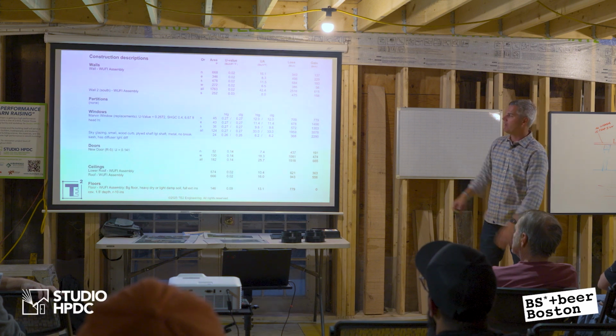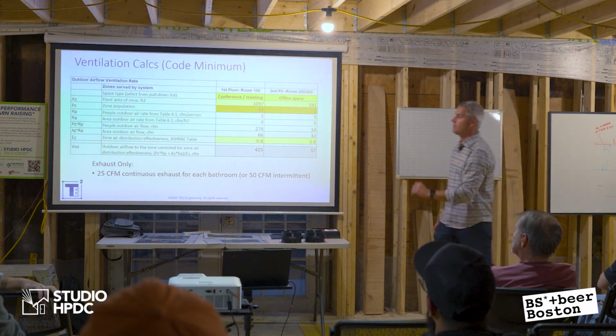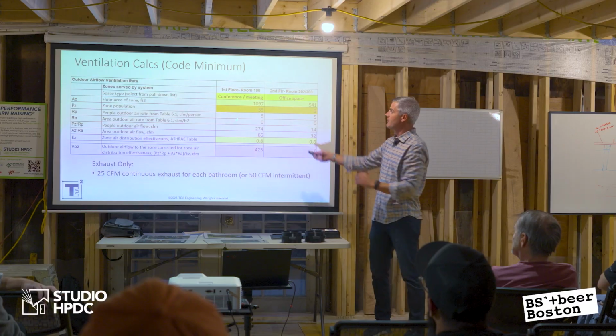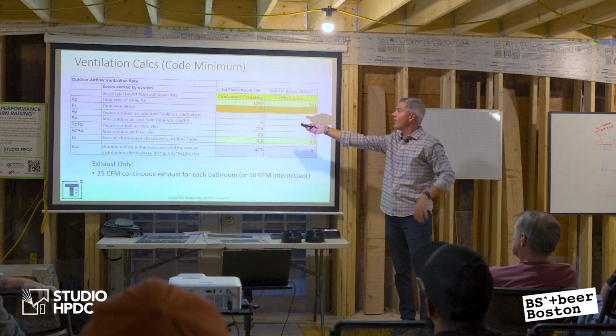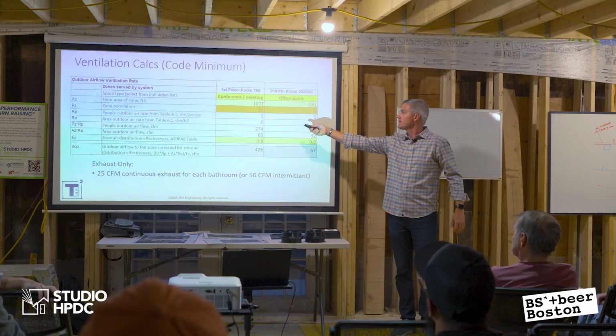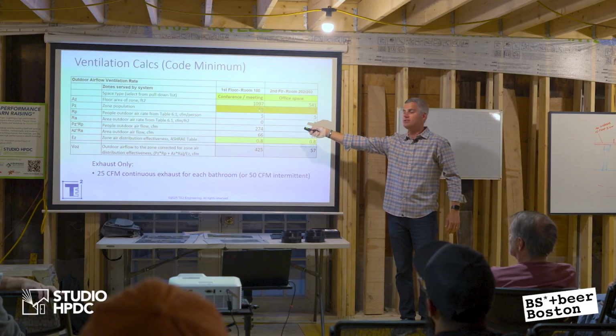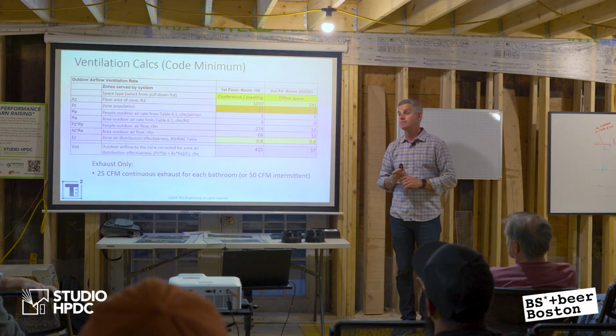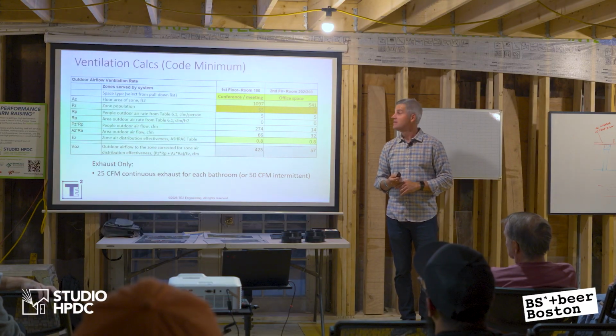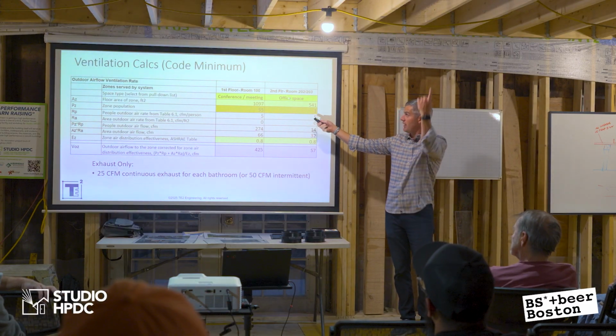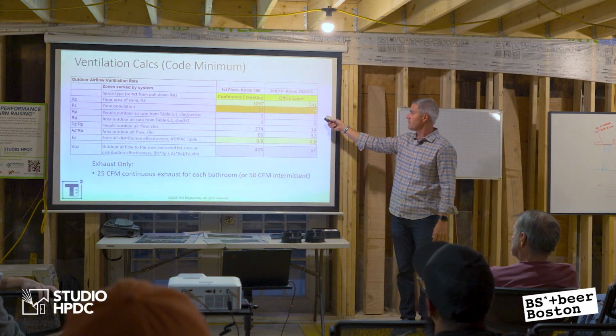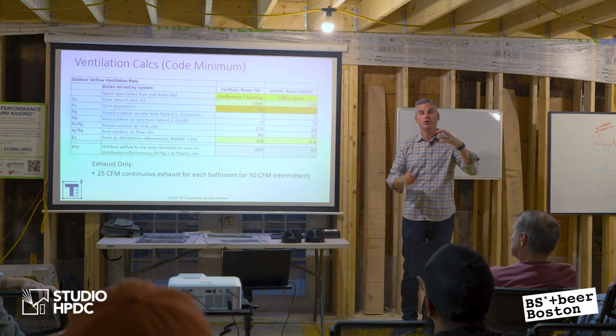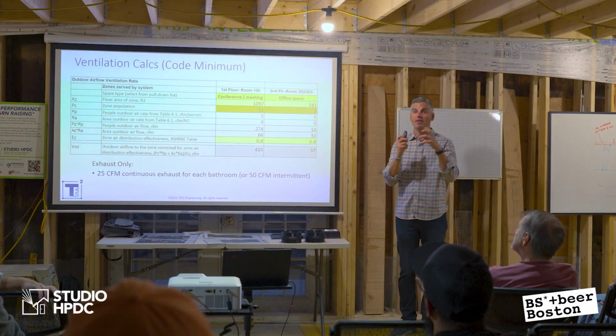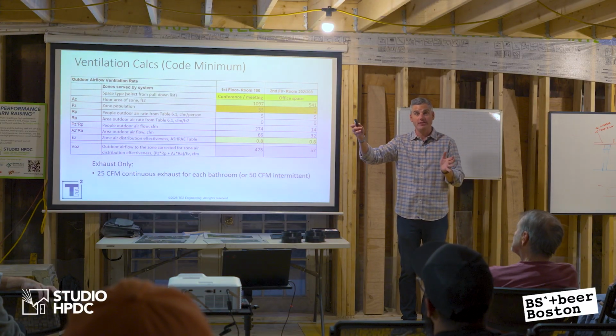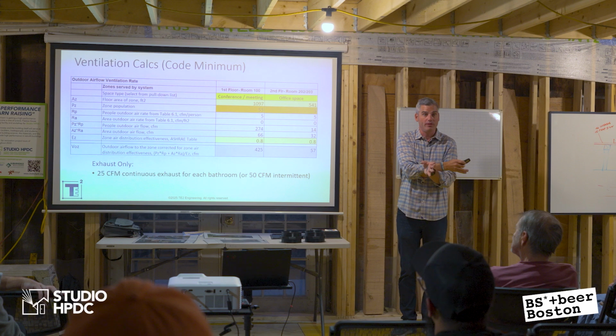I'm not going to bore you with all the assemblies, but let's start with ventilation. If I look at the code minimum, and define this room that we're in right now as a conference meeting room, the code is going to tell me that my population is 55 people in this zone. We're pushing that tonight, might be. If I define upstairs as an office space, it's 541 square feet, it's going to tell you it's 3 people. The occupant density is set by the code minimum. You can always increase it, but they don't want you to drop it below the code minimum.